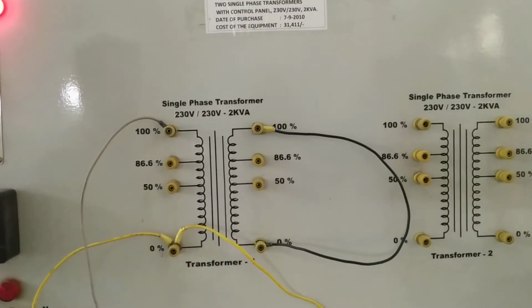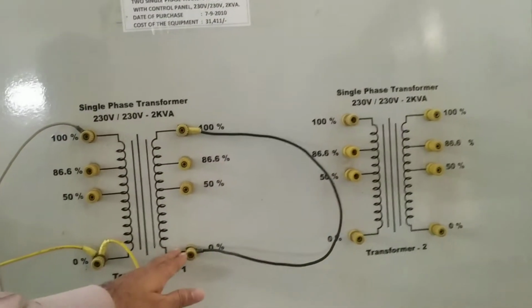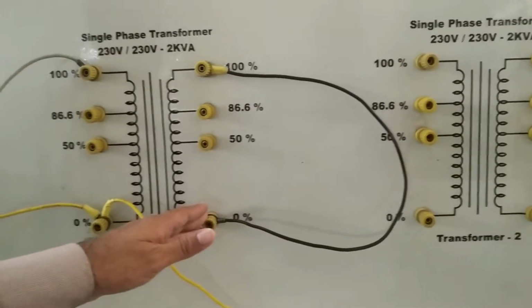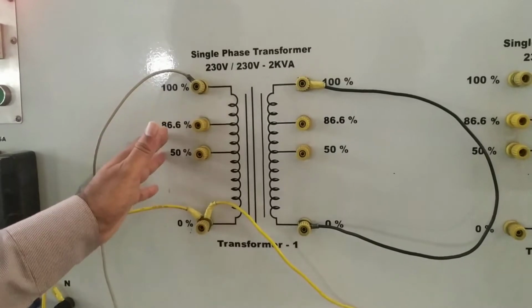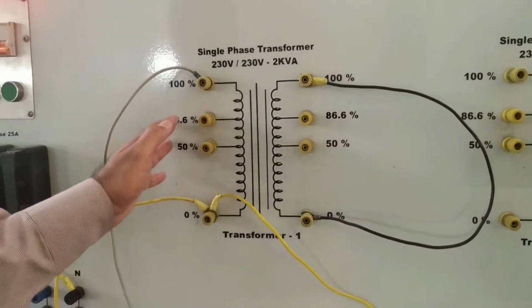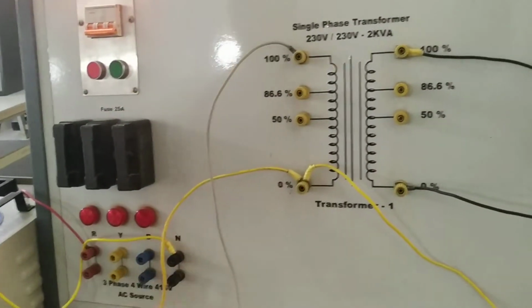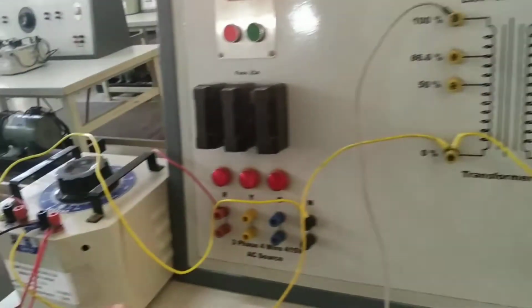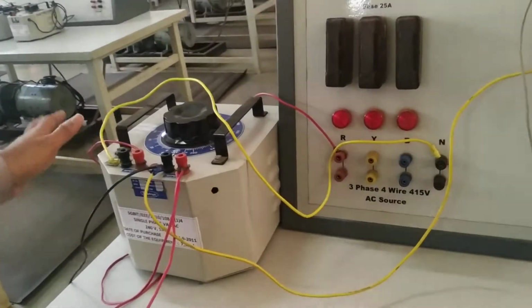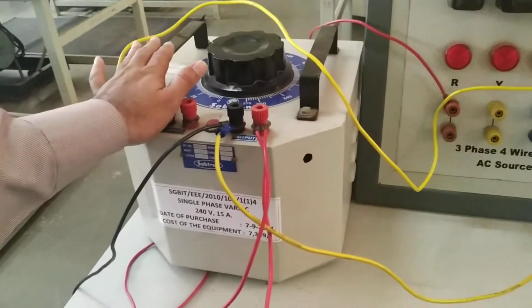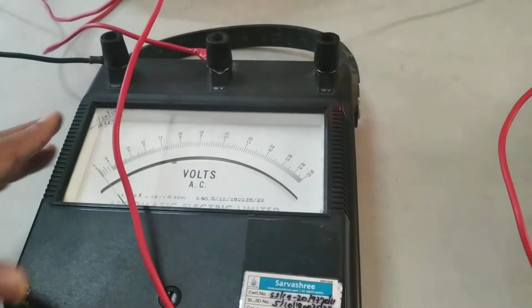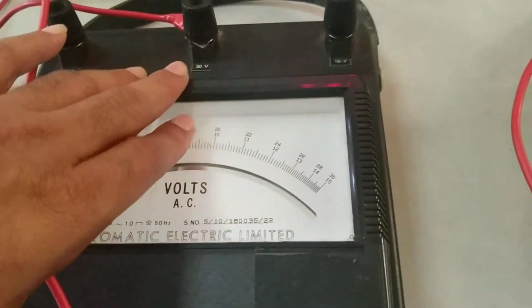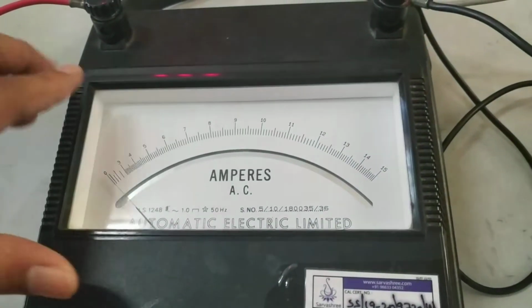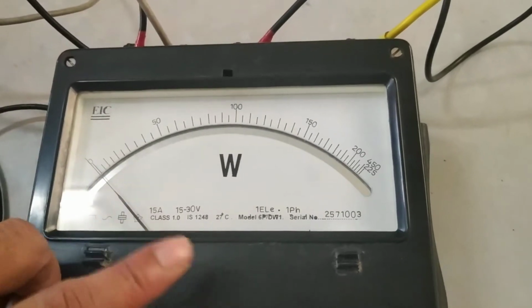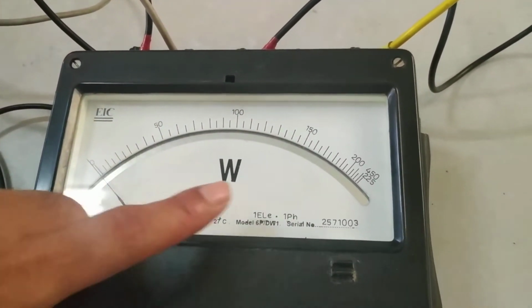During this short circuit test, we need to short one end of the transformer. Usually the secondary side is shorted, and we apply a reduced amount of voltage to the primary of the transformer. To conduct this test, we should have some components. The first one is a single phase variac or auto transformer, and second is a voltmeter with a range of 0 to 300 volt. We should have an ammeter with a range of 0 to 15, and a wattmeter to get the power consumed reading during the short circuit test.